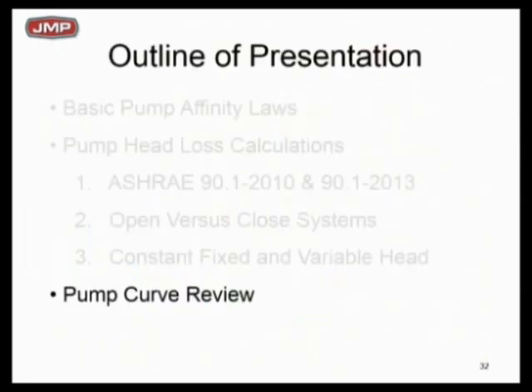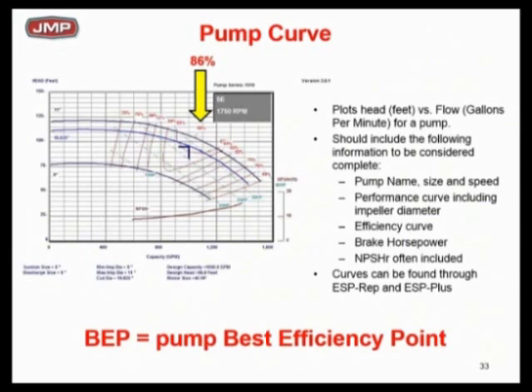Let's tie this to a pump curve review. This is what we call the Best Efficiency Point — BEP. I'm proud my pump is 86% efficiency right at that sweet spot. But the problem is it only runs there maybe 1% of the time; the other 99% it's somewhere else. So the real meaning is to look at an efficiency island — how big an area has high efficiency, and where is the pump going to be moving as the load profile changes back and forth on that pump curve.